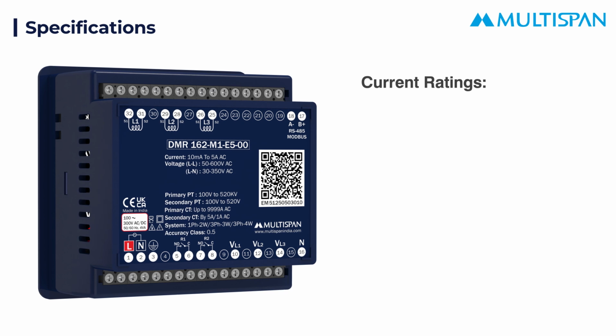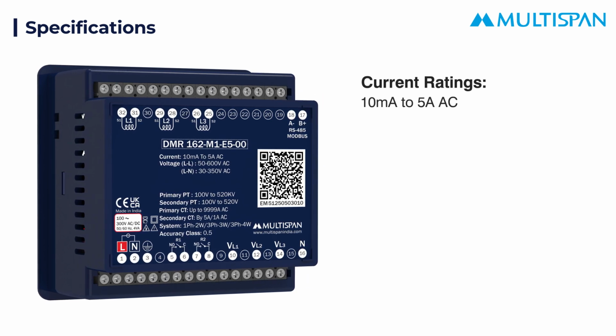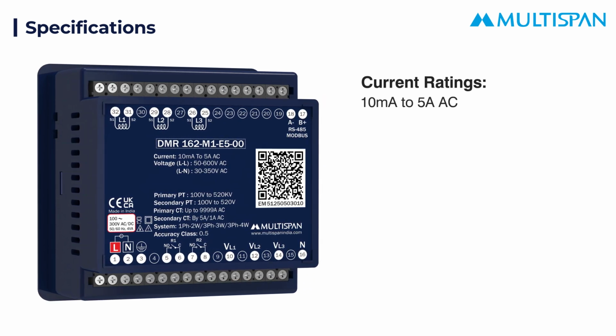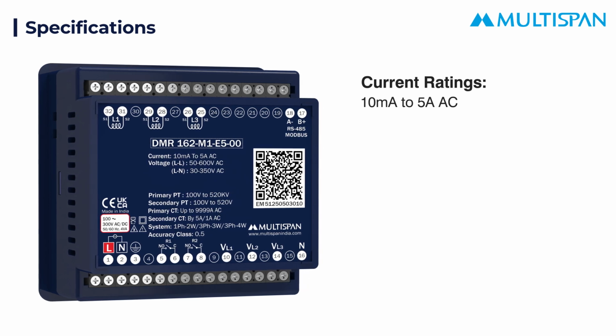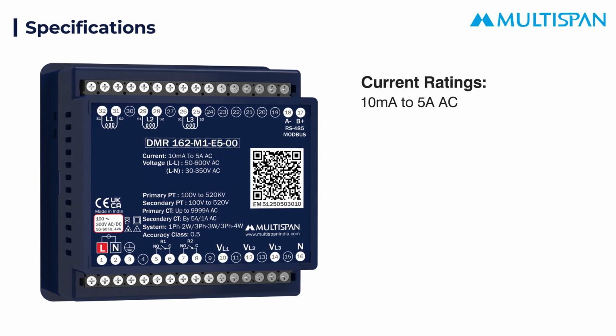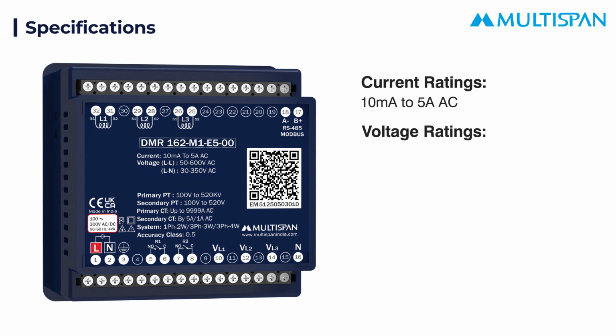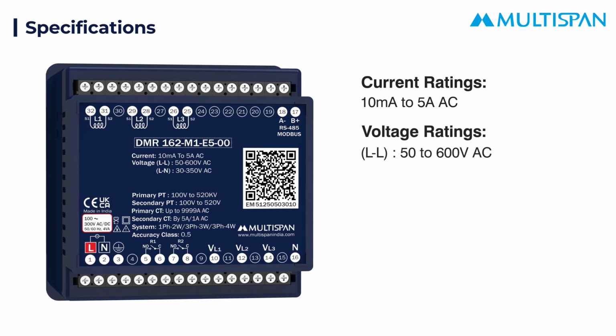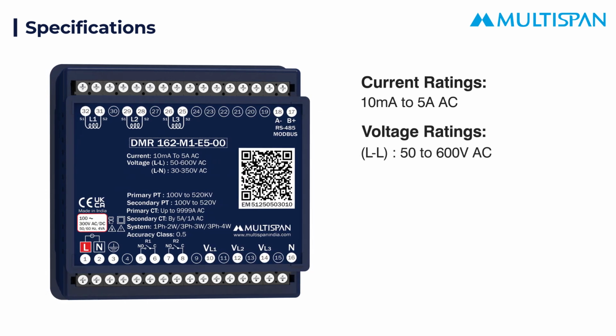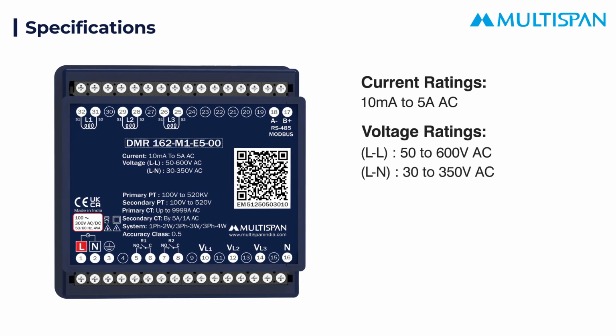Regarding current ratings, the range is from 10 milliamperes up to 5 amperes. If your CT output provides a minimum of 10 milliamperes, the current will begin registering on the display.